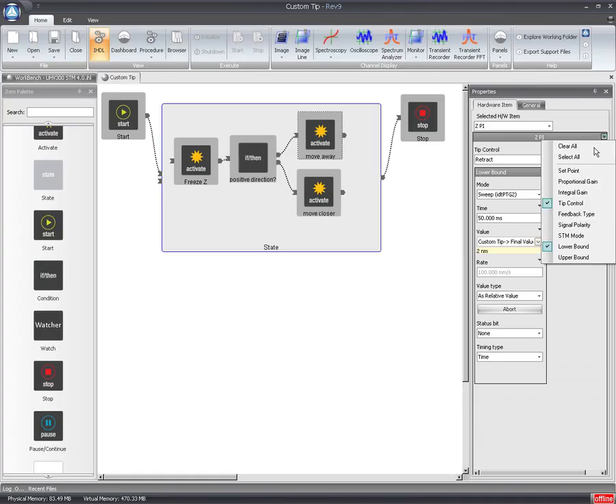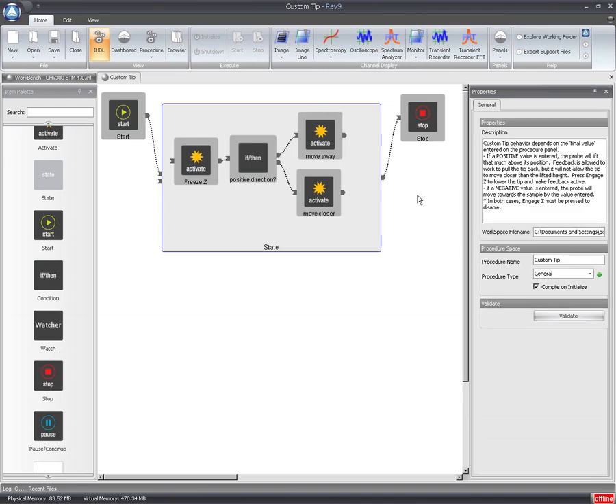Now what I've done here shows the lower bound. Our feedback loop has both a lower bound and an upper bound. So what you can think of this as is restricting the range of motion of the Z. So what I've done is allowed the tip to go no farther forward than 2 nanometers back from the surface. So it's saying pull back 2 nanometers. You can't go any farther forward, but I'm not restricting it from pulling away. So if there's any thermal drift in the system, the feedback loop is active. So I will not crash into the surface even if I drift more than 2 nanometers.